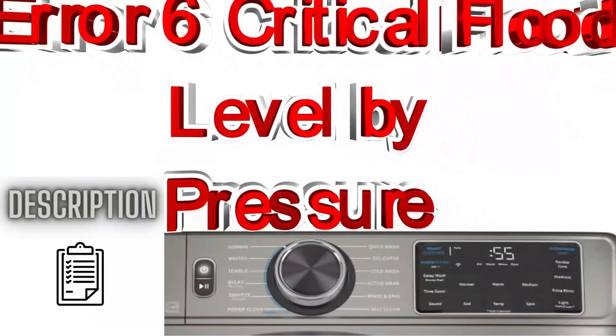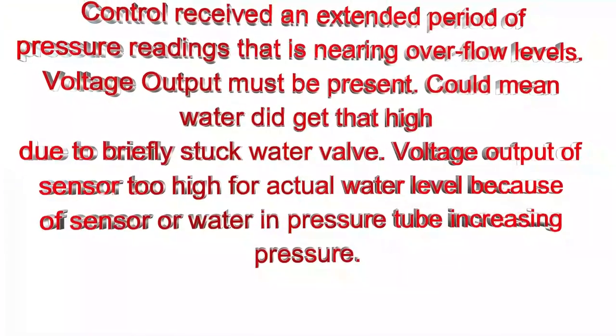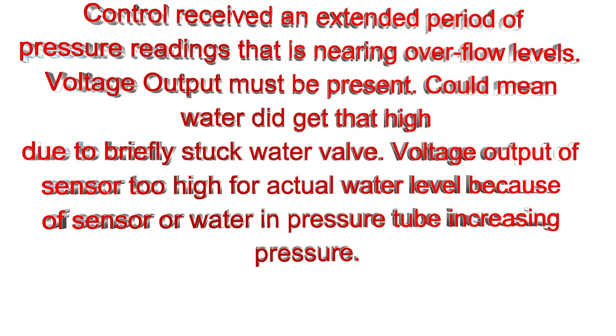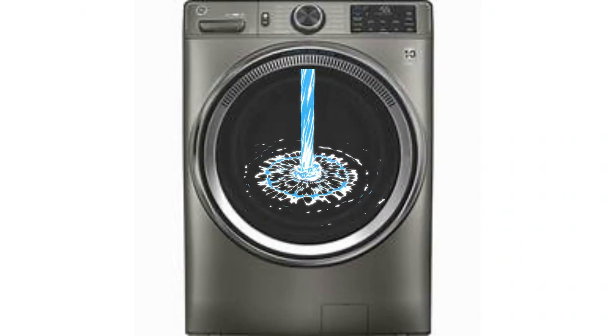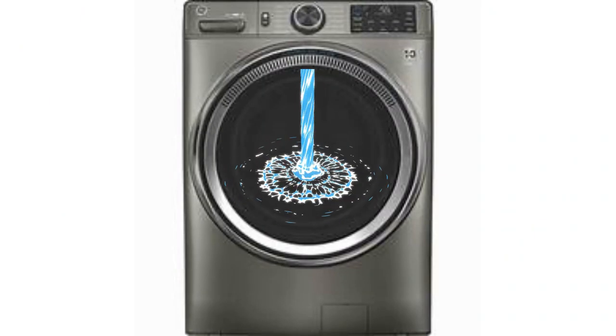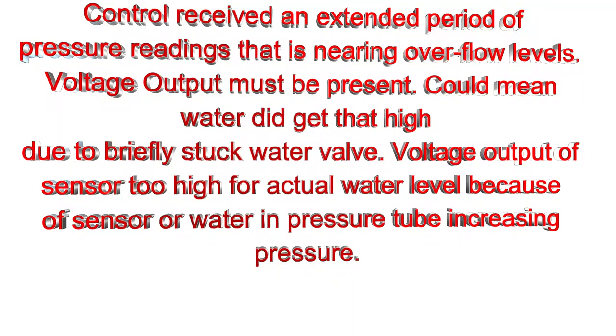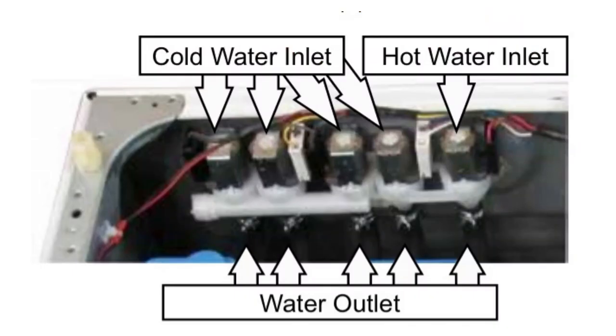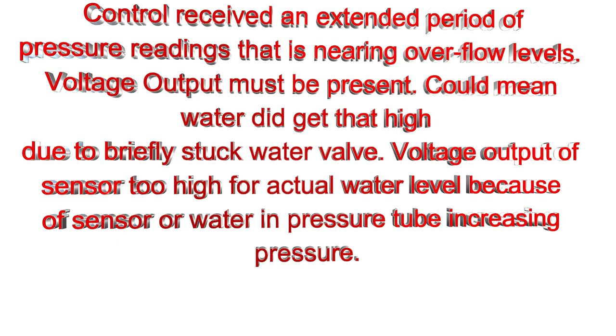Error 6, critical flood level by pressure. Control received an extended period of pressure readings that is nearing overflow levels. Voltage output must be present. This could mean water did get that high due to a briefly stuck water valve, or the voltage output of the sensor is too high for the actual water level because of the sensor, or water in the pressure tube increasing pressure.